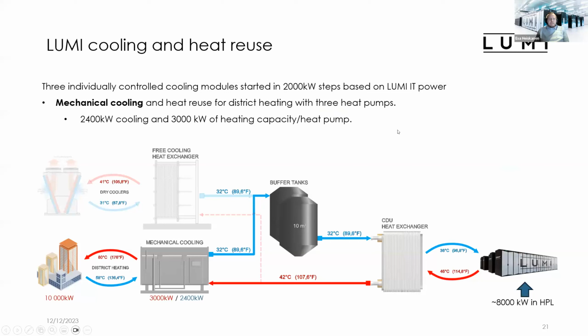So then some details about the Lumi cooling and heat reuse. So we have these 3 individual cooling modules, and this is how the mechanical cooling is operated. And when we are utilizing the waste heat from the Lumi to the district heating with the heat pumps. So each of the heat pumps has this 2.4 megawatt of cooling capacity, and with that amount of cooling capacity, those can generate up to 3 megawatt district heating. This district heating network, liquid is primed up to 80 degrees to the district heating, and it's returning somewhere about 56 degrees from the district heating network.